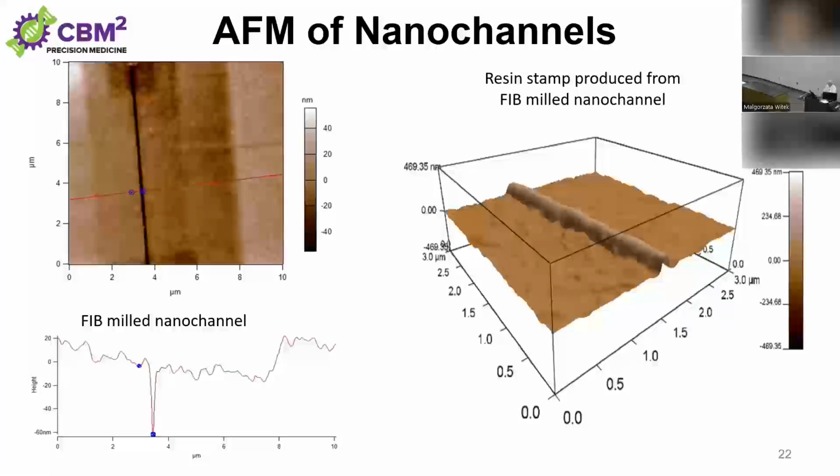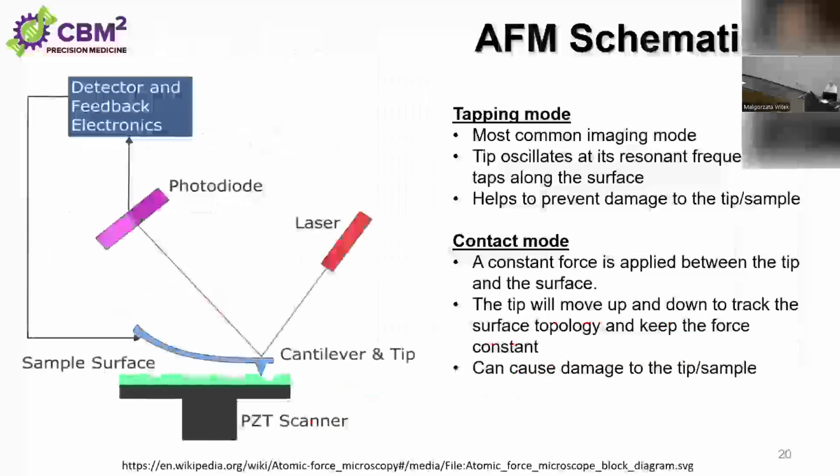So like plastics, you can easily image those with an AFM without requiring the need for coating. If you're looking at something that's several nanometers in size, and you have to put a coating on it that's several nanometers in thickness, then it's not going to work. So this obviates the need for putting those conductive coatings on, because there are no charging effects here. And let me just point out one thing here.